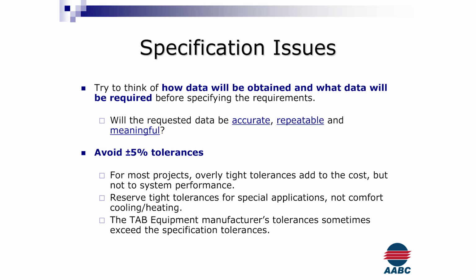Try to think about how data will be obtained and what data will be required before specifying the requirements. Are we going to be able to go out, take a traverse, and repeat that reading at the same fan speed, same RPM, same hertz? A lot of times we go out, perform tests, gather temperatures and pressures, and bring all this back to the commissioning meeting, and sometimes they only touch on a couple of things, maybe the outside air change rate or the fan speed or brake horsepower, when they've had us collect all this other data that may or may not be meaningful, and it may have just bumped up the cost of the project. So really defining what you want to see out of the data you're having us collect is important, because it lets us drill down to the detail you're looking for, instead of performing a total system balance when you only needed a few pieces of data, like relative humidity, for the troubleshooting you're doing.